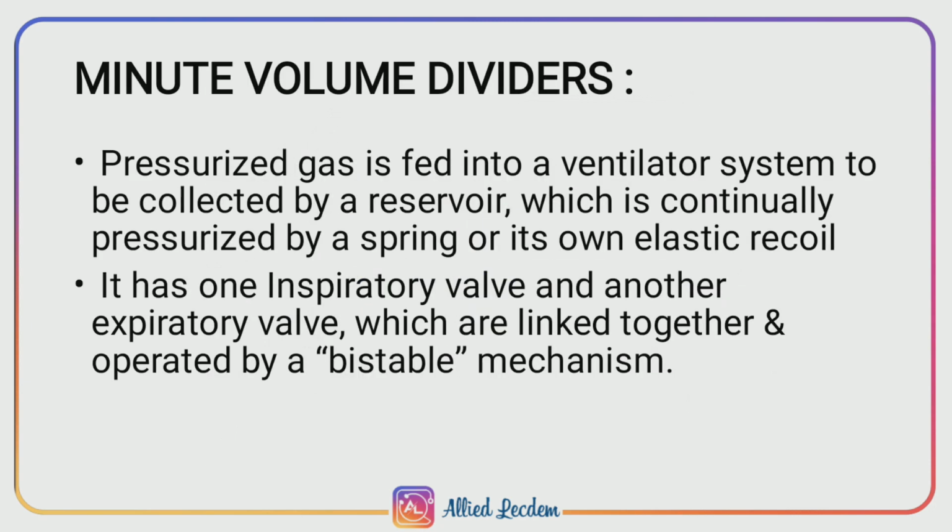Minute volume dividers. Here, minute volume is nothing but the amount of gas inhaled or exhaled from a person's lungs in 1 minute. The anesthesia machine delivers a steady flow of anesthetic gas at a set rate, which is known as the minute volume. The steady minute volume flow of gas from the anesthesia machine is divided into tidal volumes by a piece of apparatus which is known as a minute volume divider.